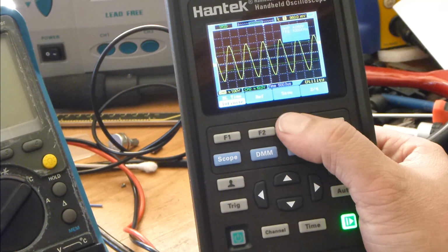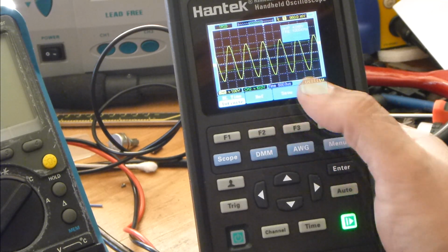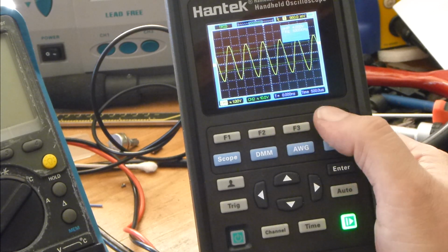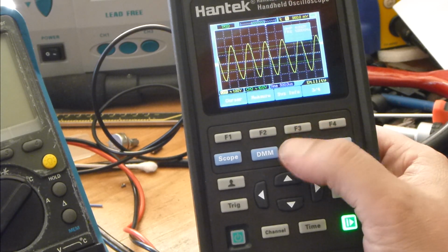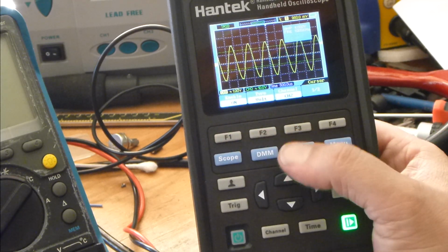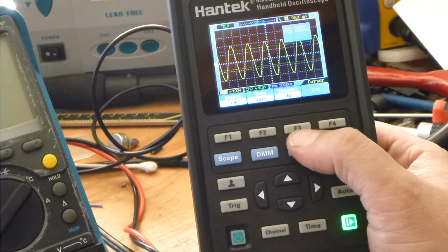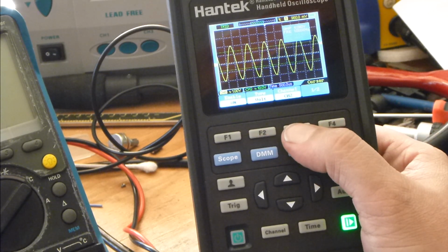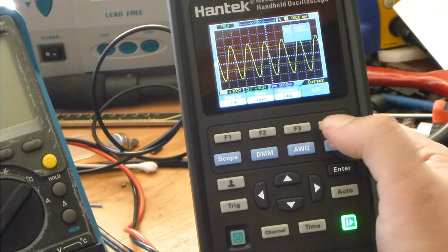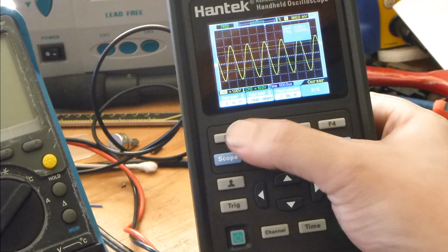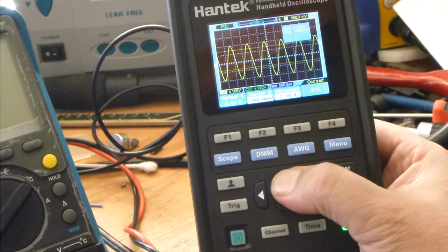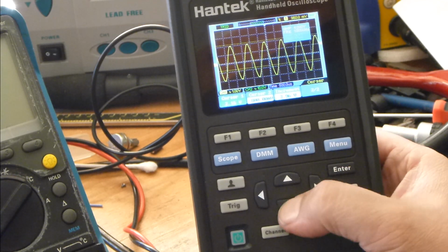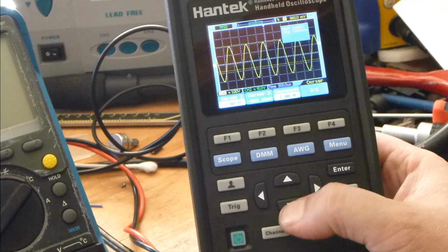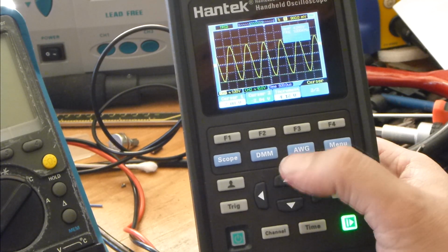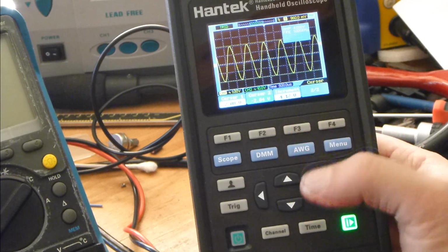We can save waveforms, and then we can use those waveforms as a reference waveform later. And this will store 6 different waveforms, so that can come in pretty handy. We have cursor measurements, so we can go ahead and go into our cursor. We can select whether we want time or volt. We can select what channel, and obviously we're only using channel 1 right now, but you're able to enable or disable it there. And then we can move our cursor, so you just select the cursor that you want to move and press up or down, and if you just press and hold, it'll move rather quickly, and then you can just adjust it. So if we want to set our other cursor, we can just pull it down like that, and that's pretty close. It's giving us an increment of 4.12 volts. So it's nice. I like it.